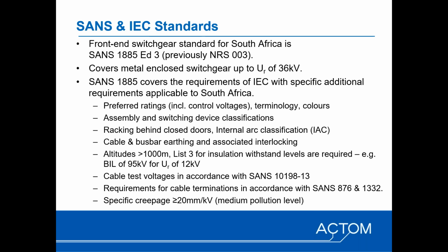People may not be aware, but the requirement for racking behind closed doors is not actually a mandatory IEC requirement, it's a recommendation, nor is internal arc classification mandatory. It's a special test, but SANS 1885 effectively makes, or switchgear designed to SANS 1885 requires racking behind closed doors if it's of the withdrawable type, and internal arc classification, and it provides the parameters.